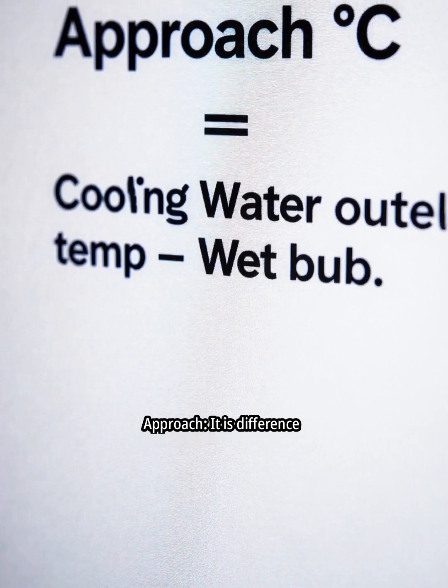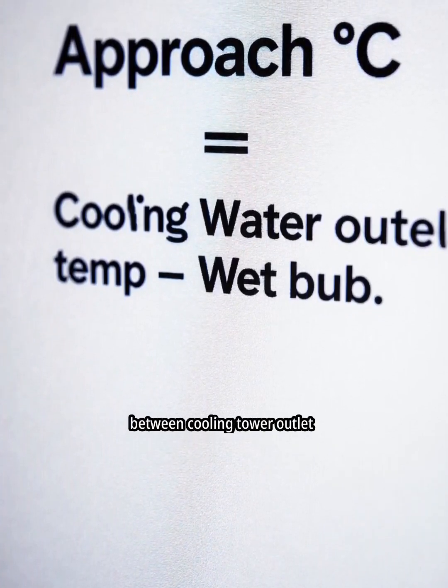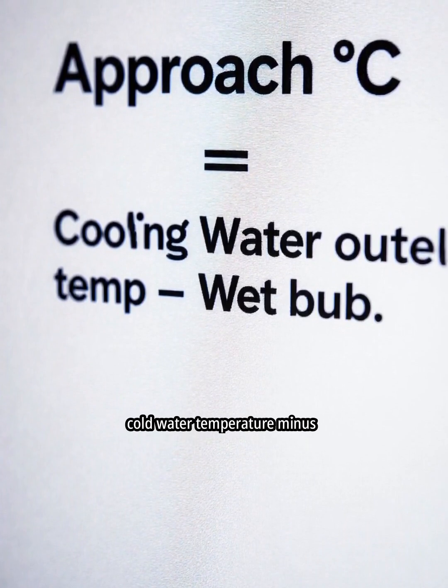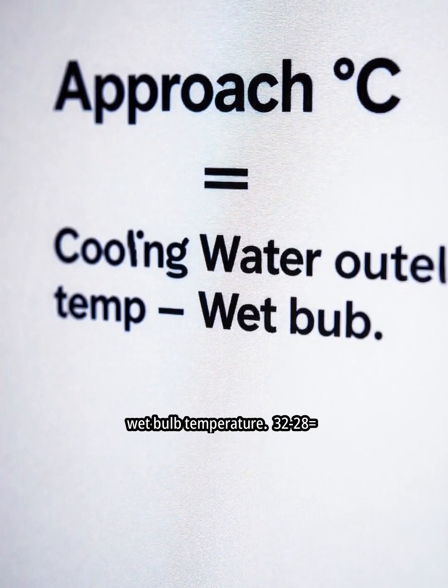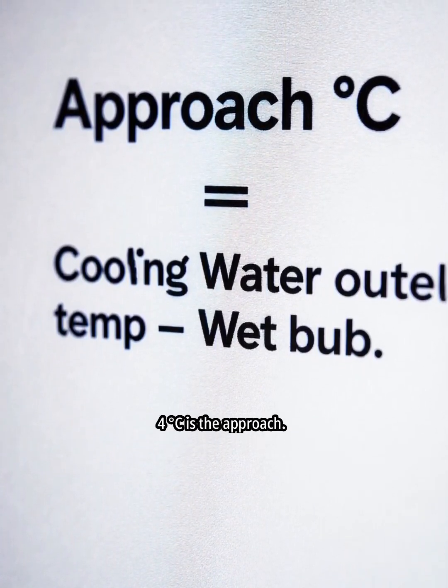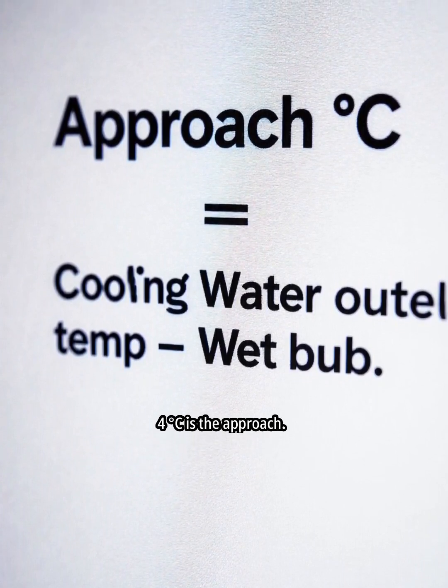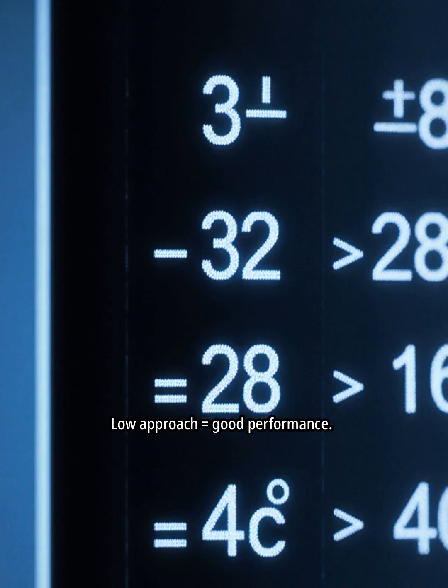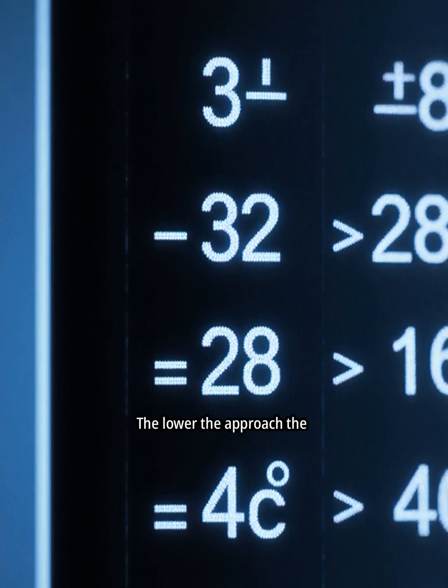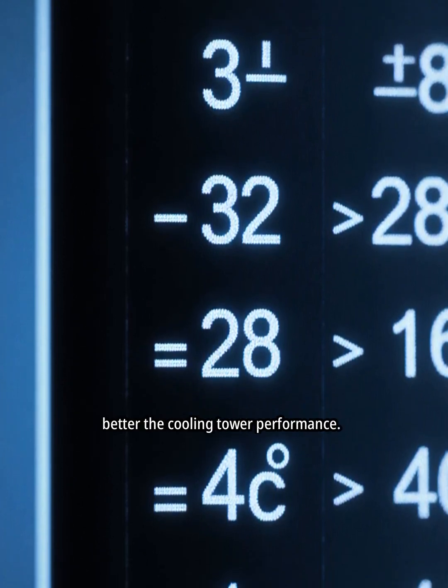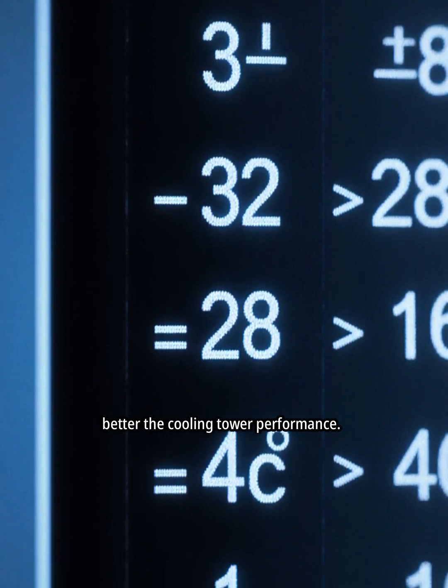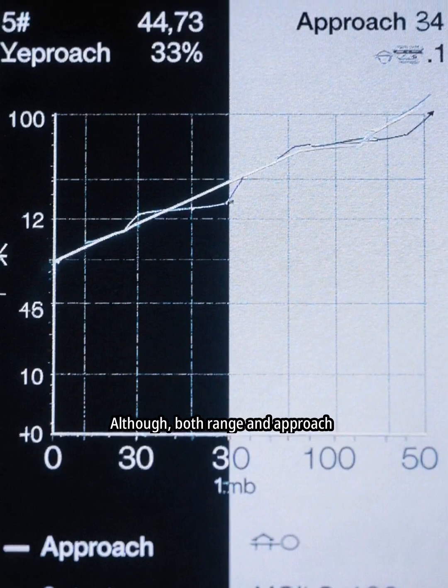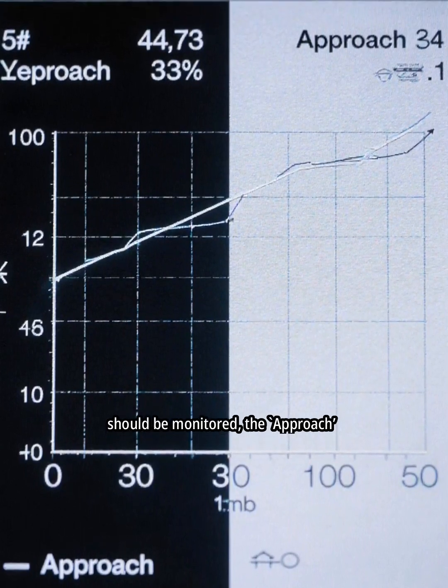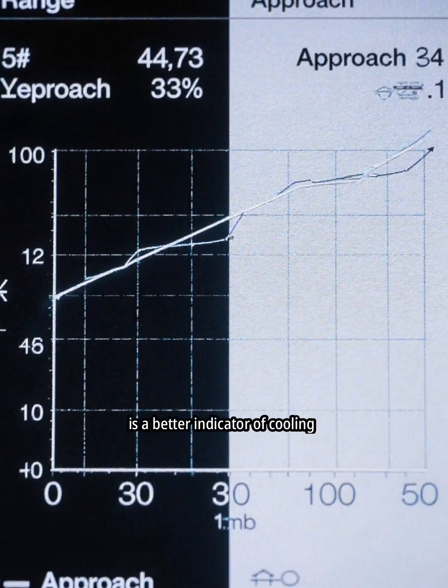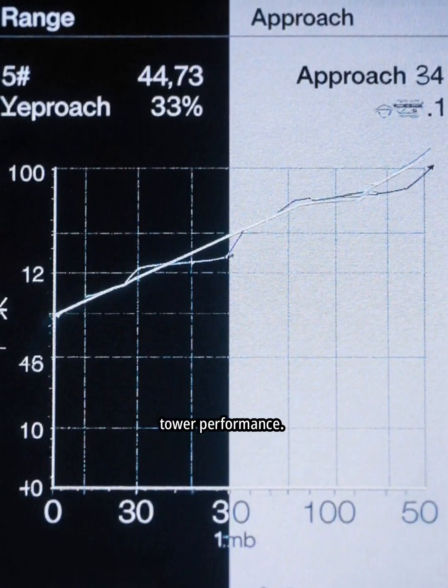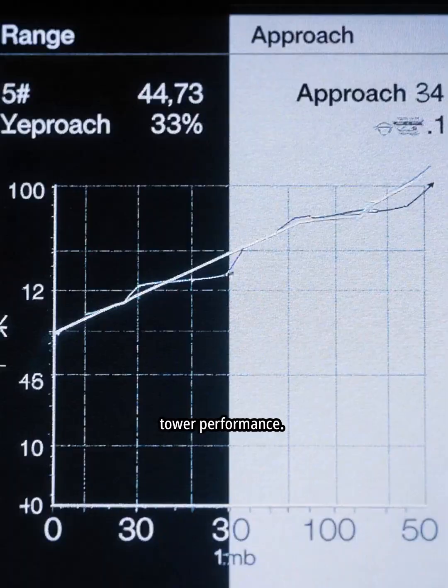Approach. It is the difference between cooling tower outlet cold water temperature and wet bulb temperature. 32 minus 28 equals 4 degrees Celsius is the approach. Low approach equals good performance. The lower the approach, the better the cooling tower performance. Although both range and approach should be monitored, the approach is a better indicator of cooling tower performance.